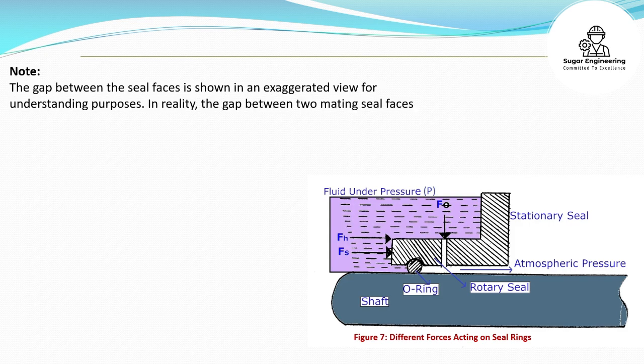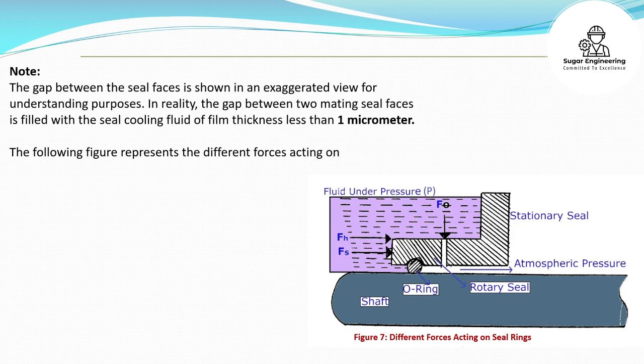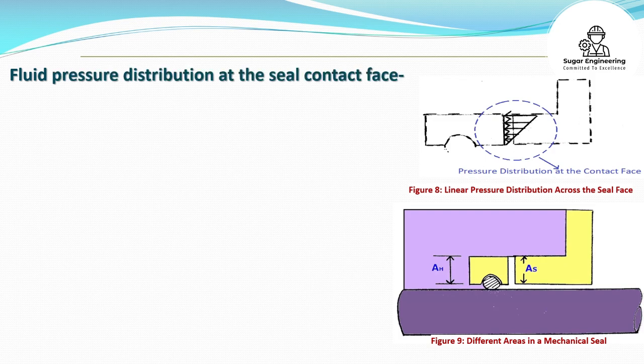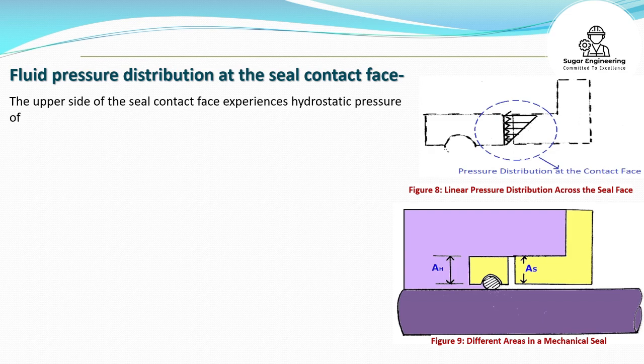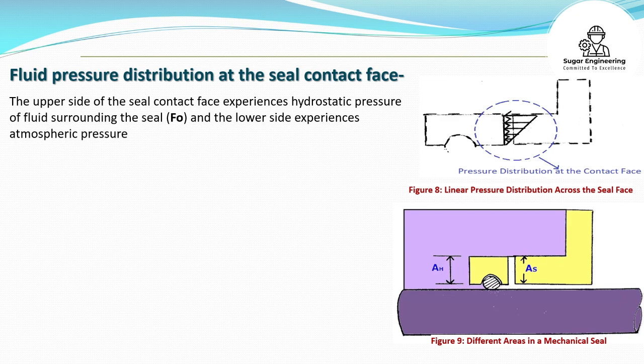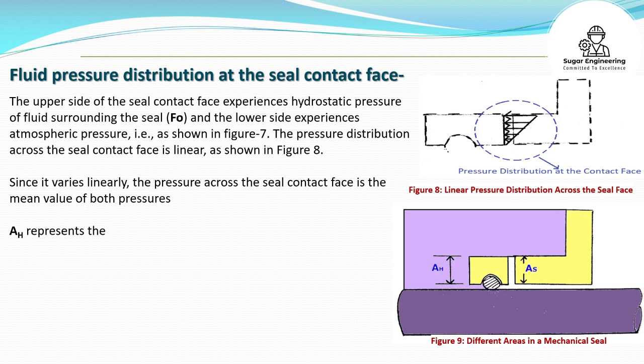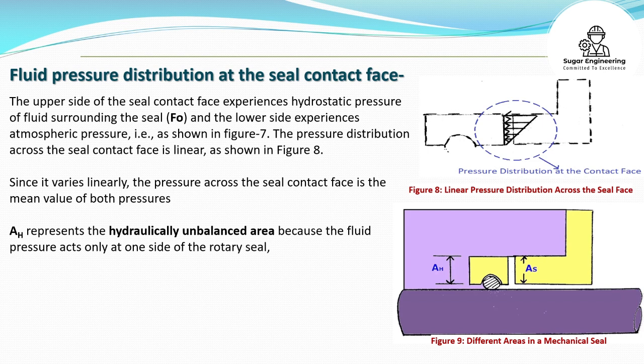In reality, the gap between two mating seal faces is filled with a seal cooling fluid of film thickness less than 1 micrometer. The following figure represents the different forces acting on the seal rings for effective sealing, where FO represents the seal opening force, FH represents the hydrostatic force, Fs represents the spring force, and P represents the fluid pressure. The upper side of the seal contact face experiences hydrostatic pressure of the fluid surrounding the seal (FO), and the lower side experiences atmospheric pressure, as shown in Figure 7. The pressure distribution across the seal contact face is linear, as shown in Figure 8. Since it varies linearly, the pressure across the seal contact face is the mean value of both pressures. AH represents the hydraulically unbalanced area, because the fluid pressure acts only at one side of the rotary seal. As represents the seal face contact area.